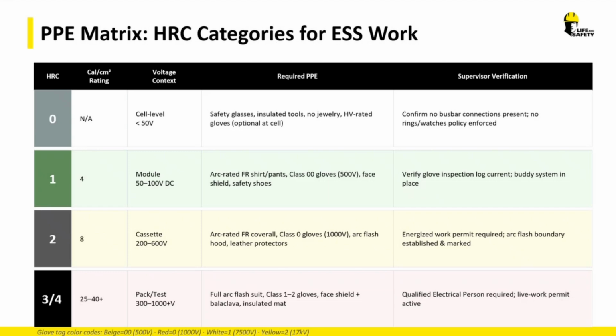I get a question quite often about the gloves and removing leather protectors. The code does allow this, but it's important to know that within that same exception allowing the leather protector to be removed for fine instrumentation work, meaning delicate work requiring dexterity, you must derate the glove by 50%. So if it's a 500-volt glove, it's now a 250-volt glove. If it's a 1,000-volt glove, it's now a 500-volt glove. That only applies as long as the leather protector is off. Once you put it back on, it goes back to its full voltage rating. So that's the quick rundown on the glove problem.